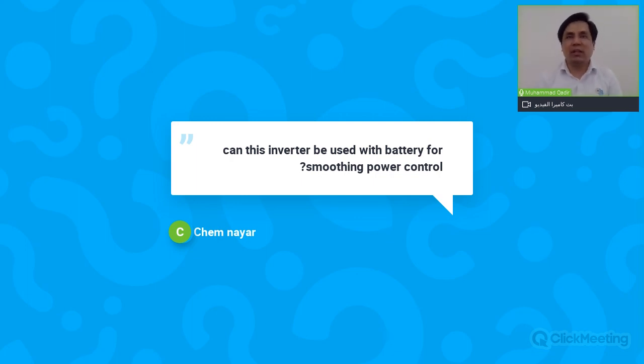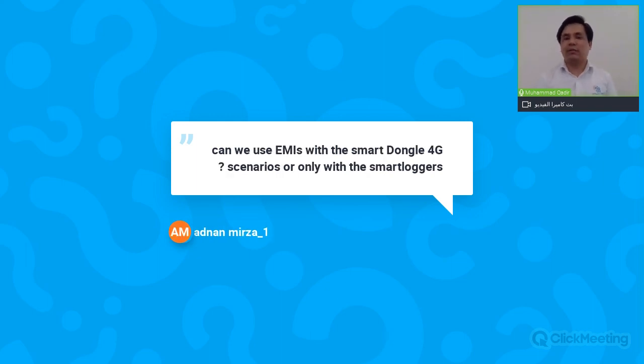And when there is grid available in the evening and your load is high, your generation from solar is less, you can use a combination of your solar generation and the battery in order to run the load. Later in the evening, when there is no solar, if your battery is still charged, again you can use the battery to give power to the load. But if the grid goes off, this inverter will not work because the grid is always required since Huawei inverters are on-grid. In the near future, Huawei is going to be introducing special new inverter versions where Huawei will also provide their own battery series along with the inverter, which can also be used for off-grid application.